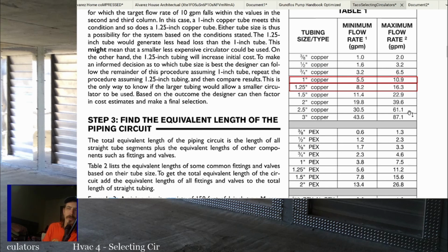And by the way, this is a pretty good estimation of how much flow you can get through a pipe. So if you're working on a water source heat pump or a coil, and you need so many GPM through it, and you're thinking maybe they sized the tube too small, this little table is pretty handy. You can do the math for it, but this is a handy table if you're not used to it. For going, okay, how much flow can I get through a 3/4 pipe? If it says it needs 4 GPM, can I get 4 GPM through a 3/4 pipe? And yeah, we're within a range for 3/4 pipe on GPM, and so on and so forth. So if you ever wondered how many gallons of water you can get through a pipe, you can get a lot more than this on a higher pressure plumbing system sometimes, but these are still pretty good GPMs to figure on anything that's circulating.